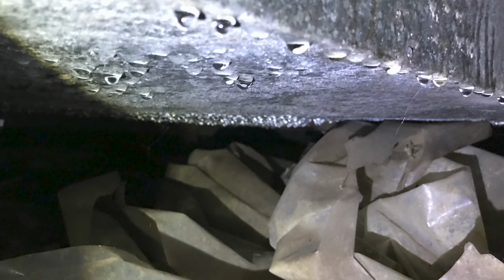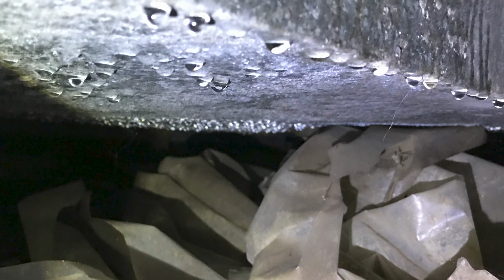So if you've recently had an HVAC system upgraded with one of these new high SEER units, there's a good chance that if they didn't replace the ductwork, didn't upgrade the insulation, and there was no dehumidifier installed, that new HVAC system can cause all kinds of condensation on the ductwork and dampness to explode inside that crawl space.